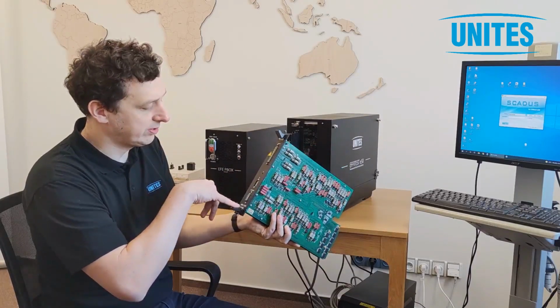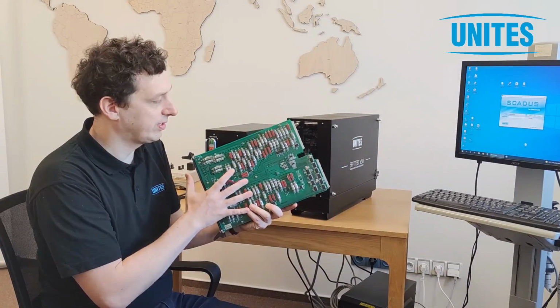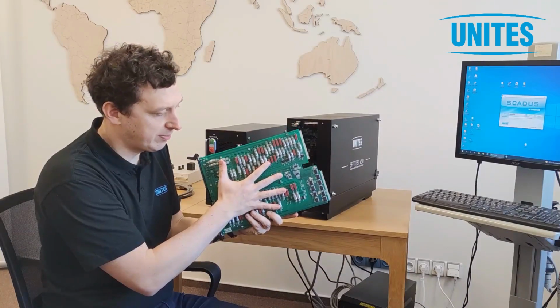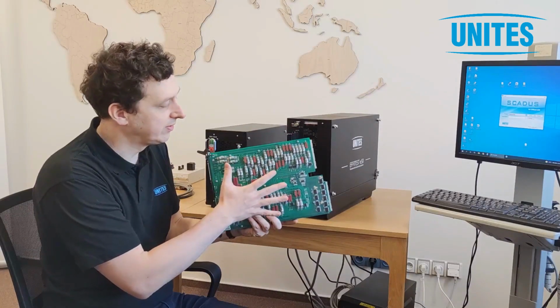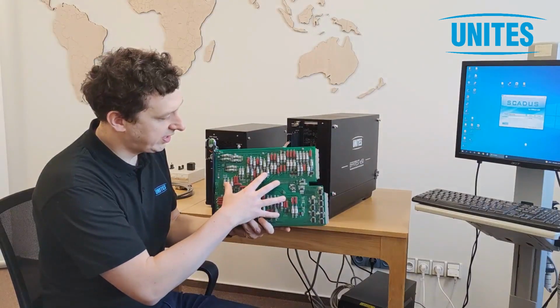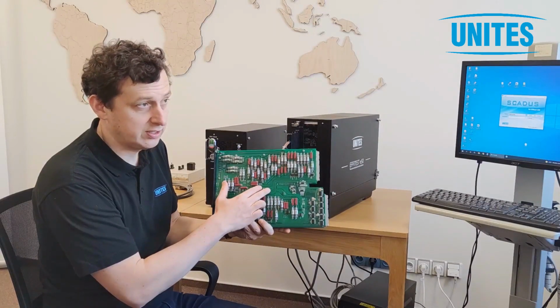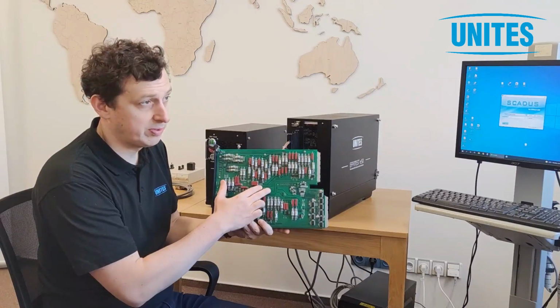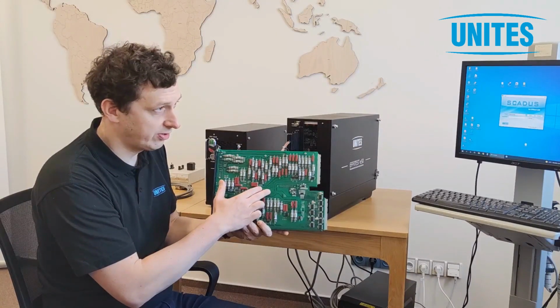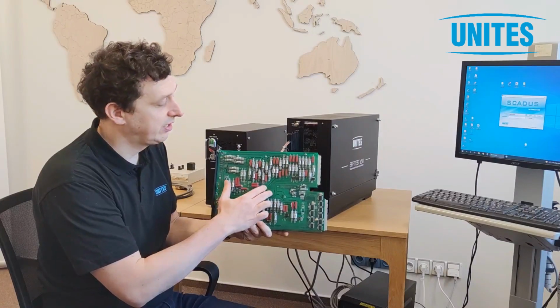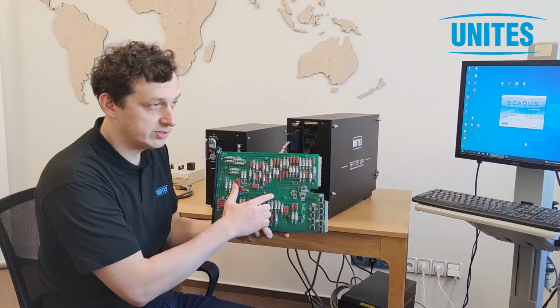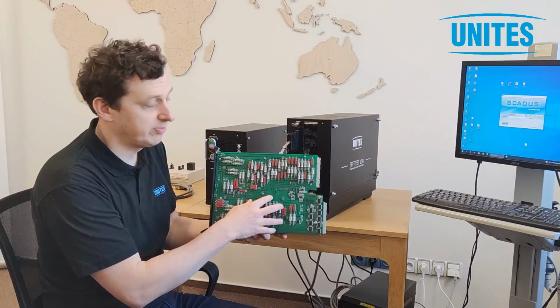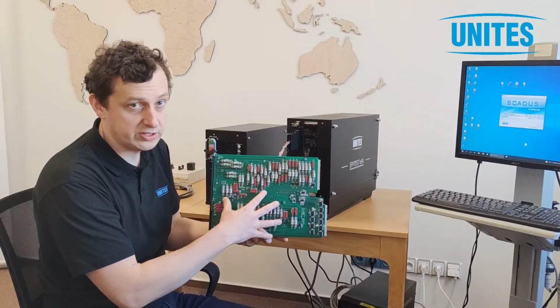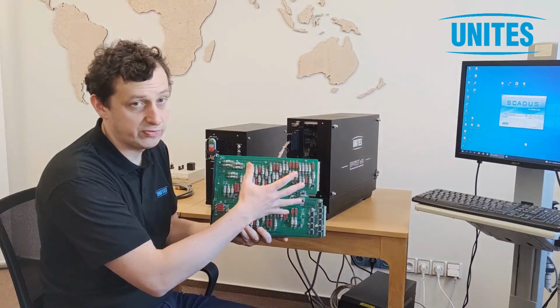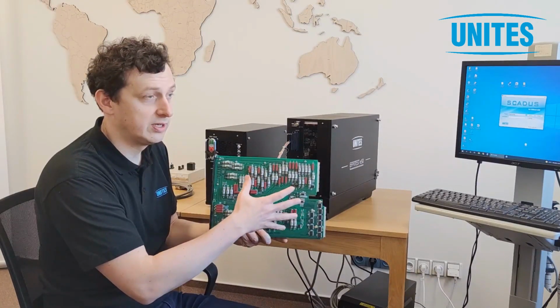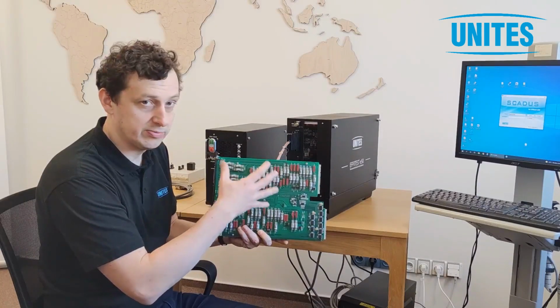One is what we call a CVI, fully capable of testing one test position on the handler. One CVI consists of two VIs, voltage current sources, capable of forcing and measuring 30 volts and 3 amps each, one high voltage source of 600 volts, and a leakage current meter. All sources have digitizers, so you can display in the software the waveforms of the power supplies and the measurements themselves.